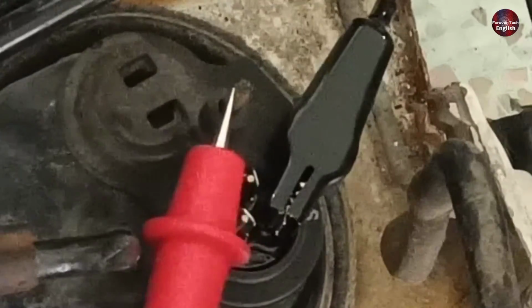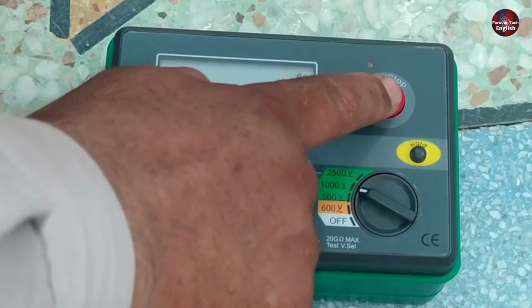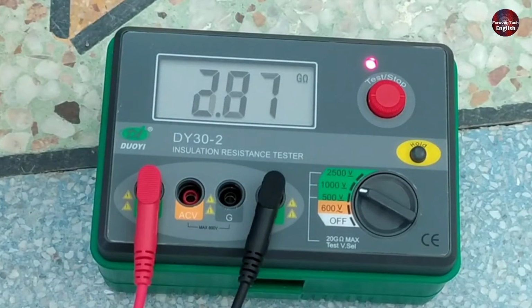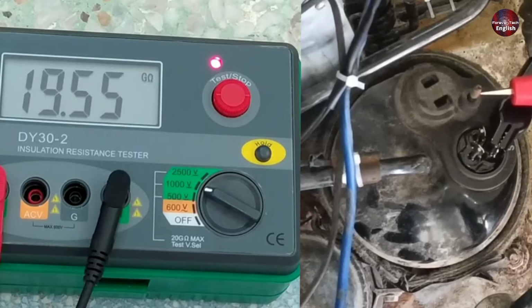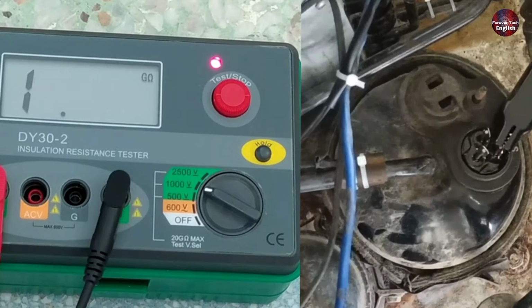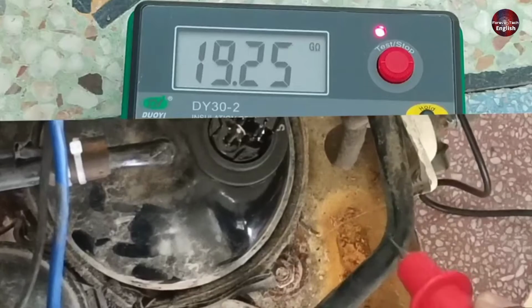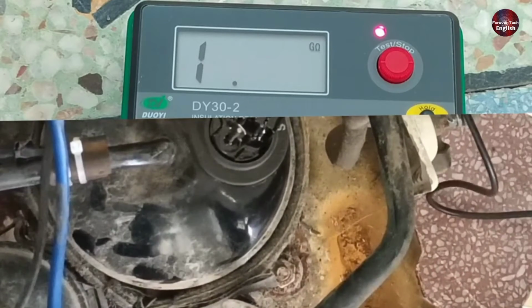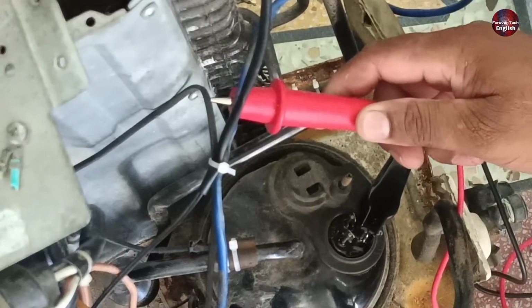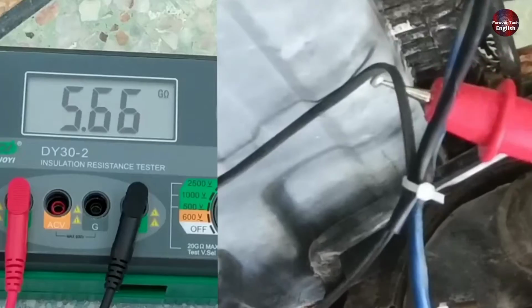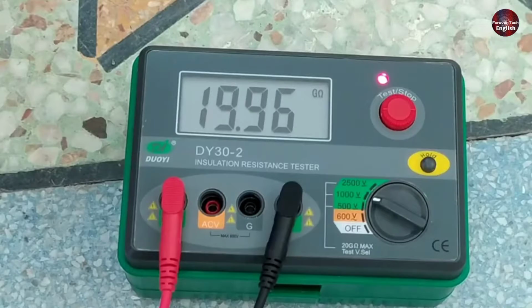I have attached it here, and I press the test button again. Let's see how much resistance it has. The reading is almost 20 gigaohms, and then it disappears, meaning it has no short with the body. See if I touch the probe with the copper as well. It still shows the same reading. Or if I touch it with the body of the outdoor, it still shows the same reading. This means the winding of the first terminal is fine.